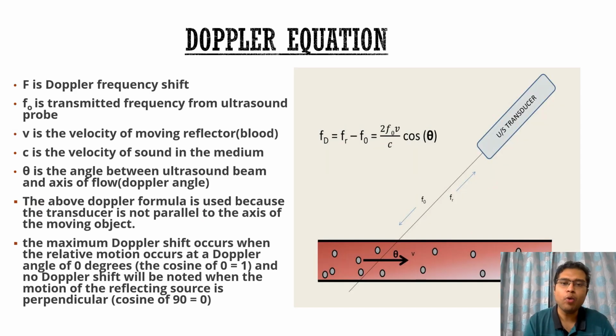So coming to this very important Doppler equation, which helps us calculate the velocity of the blood flowing within a blood vessel because of the Doppler shift or Doppler effect. So Doppler shift is equal to the received frequency minus the transmitted frequency, which is equal to 2 into the transmitted frequency into V, that is the velocity of the blood, divided by C, the velocity of the sound within the medium, into cos theta. Theta is actually the Doppler angle, that is the angle between the ultrasound beam and the axis of the flow.